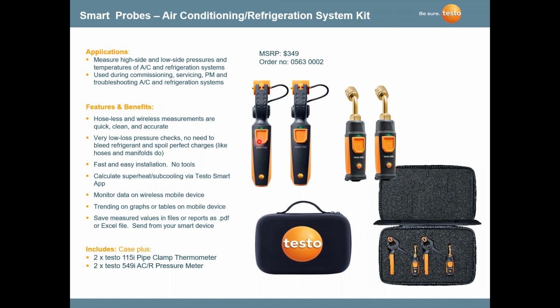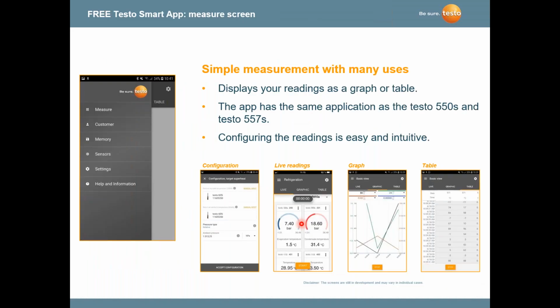For instance, if you don't want to use hoses at all, you just want to use an app and you don't want to go through a digital gauge, this would be considered a quick test of superheat and subcooling. You have two pressure probes, one on high side, one on low side, two pipe clamp probes, and you notice there's no display or anything. Well, that's because we're using our smart device to capture the readings. And once we capture the readings in our smart device, there's a lot of different things we can do with it. We can record the readings, we can graph the readings, we can send the readings, email. We can do a lot more calculations.